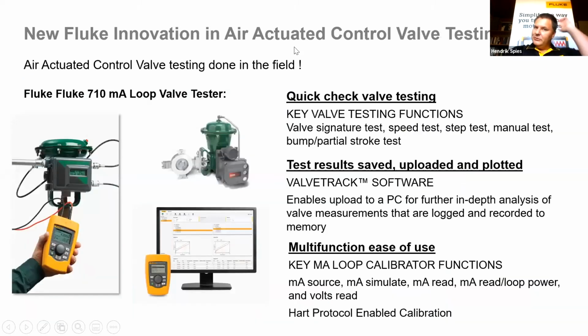The third product we want to introduce to you is more in our process tools portfolio. If we look at air actuated control valves in the field, this is typically an example. There's quite a lot of them on customer sites. And what we've done is we've built a specific tester called a Fluke 710, also called a milliamp loop valve tester. So this unit is developed to do quick testing with some key testing functions like basically signature test, which you can see some graphical information here, speed test, step, manual test, bump, and partial stroke test.